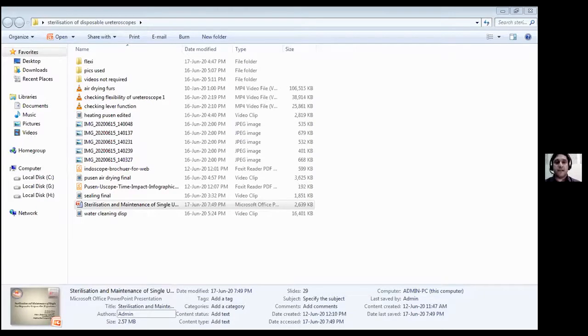So after sealing it, we put it in the Sterrad 100NX, which is an H2O2 plasma sterilizer. Now it is bactericidal, virucidal, and fungicidal and destroys even the prions. It is a low temperature hydrogen peroxide gas plasma sterilization. The advantage is that it does not require any aeration. There are no chemical residues and there are negligible environmental concerns.